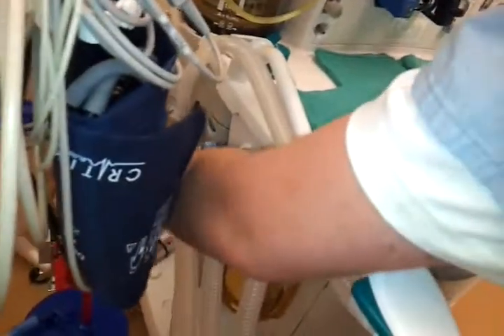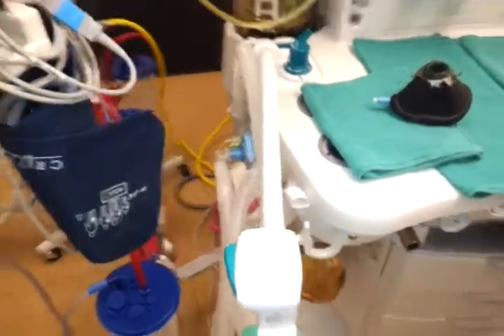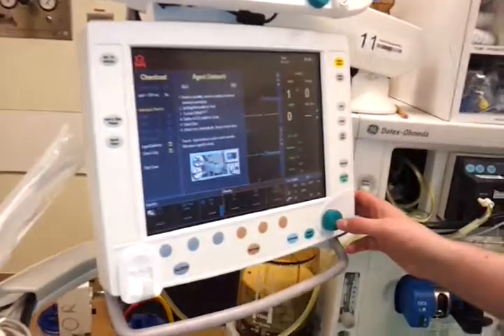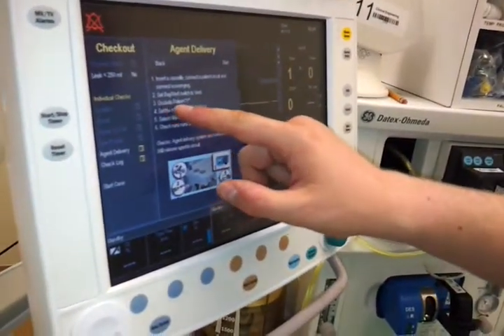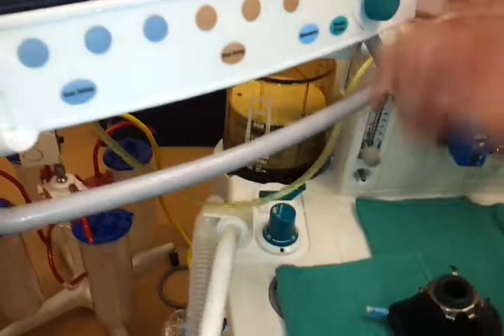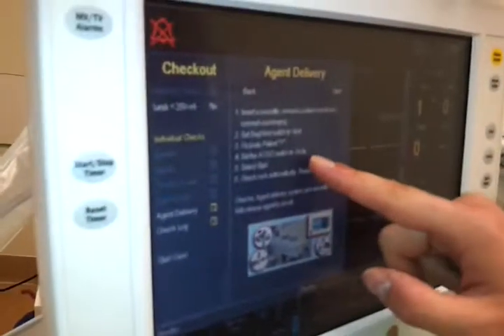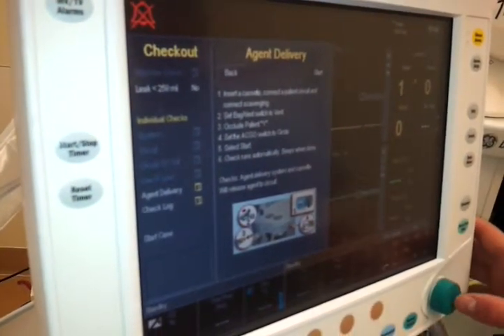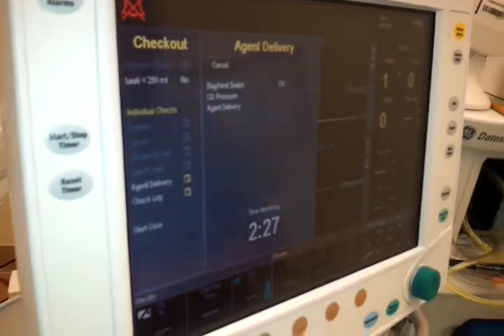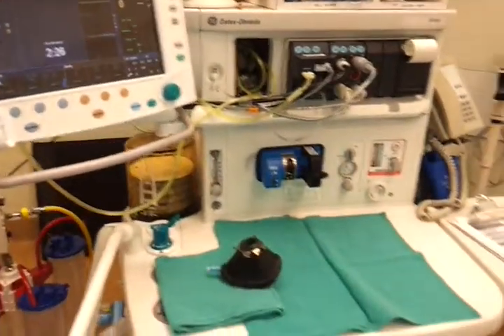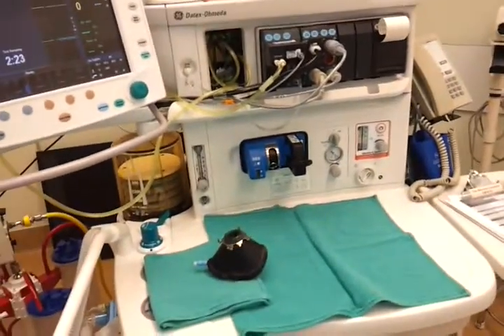Okay, so you're going to occlude the patient circuit because it's going to actually be desflurane going through, will come out the end if it's not occluded, and you don't want to breathe it in. So put it to vent, it's already on vent right here, ACGO to circle and occlude. So start. That's going to take 2.5 minutes, and while we do that, we're going to do the extra equipment we have to check. Okay, so that's in the drawers here.